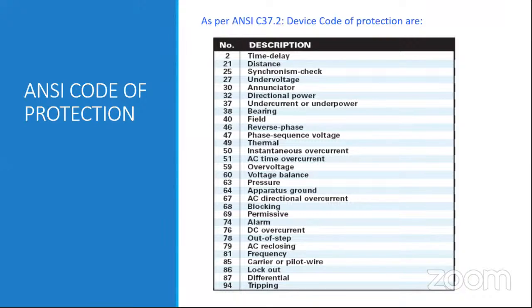37 is undercurrent or underpower. 40 is the field failure protection, which is for the generator. 46 is reverse phase, or negative phase sequence, used particularly for motor protection. 47 is phase sequence voltage: if there is a voltage shift between the three phases, this protection should come in line. Thermal protection is used for cables and motors, so that the motor or cable does not get thermally overloaded.